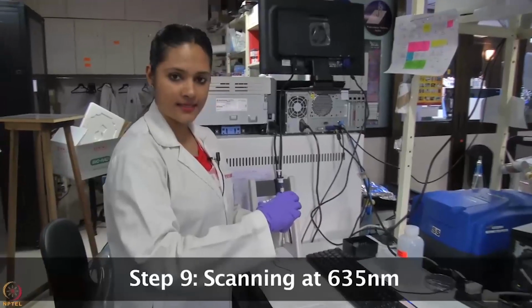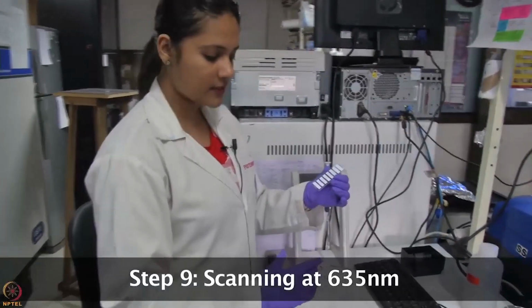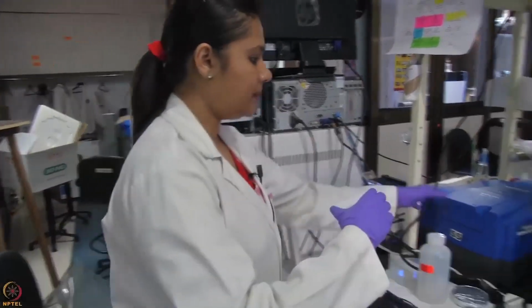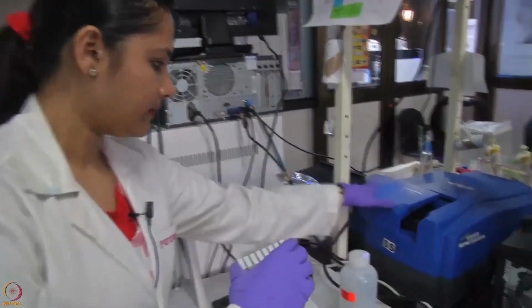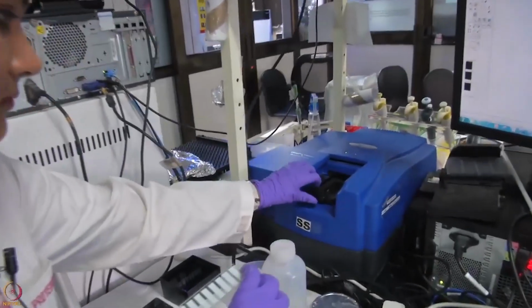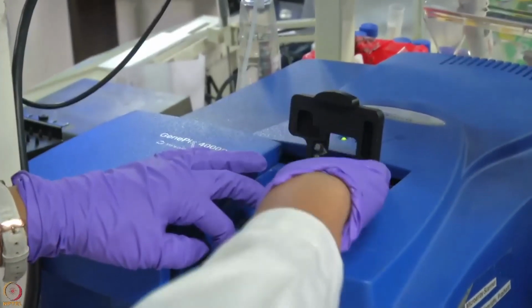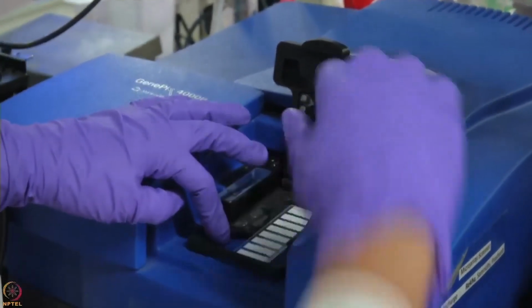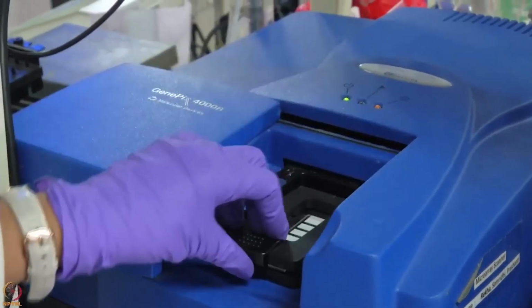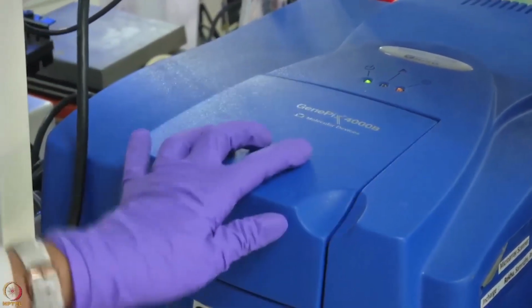So we are going to now scan the slide. As you will see, the slide is dry after centrifugation. We will place the slide carefully in the scanner with the barcode side facing downward. So now we will scan the slide.